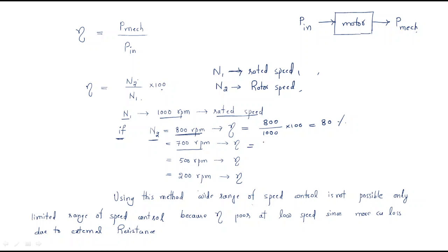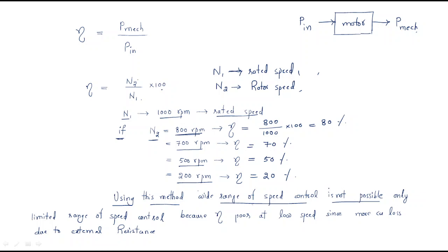If the rotor rotates at 700 rpm, then efficiency is 70 percent. If it rotates at 500 rpm, efficiency is 50 percent. If it rotates at 200 rpm, efficiency is 20 percent. So the rotor speed decides the efficiency of the motor. Using this method, a wide range of speed control is not possible — only a limited range of speed control is possible. This is an important point.